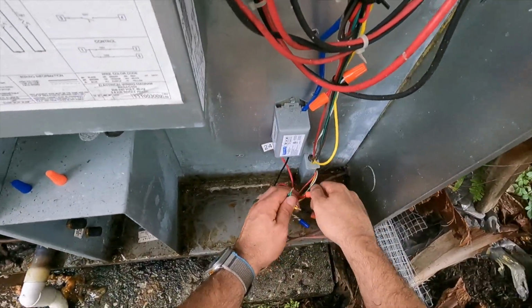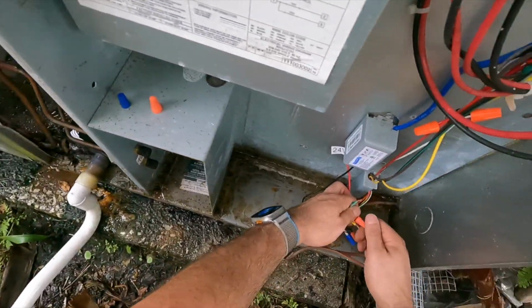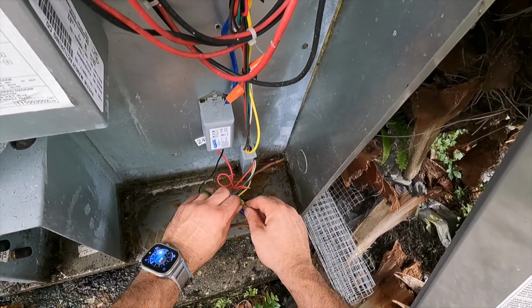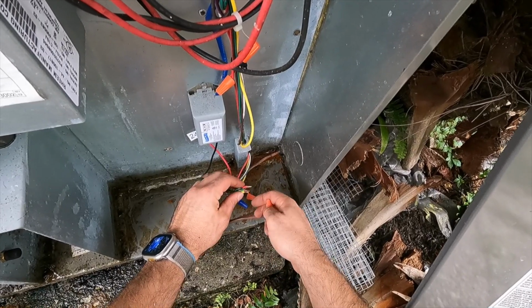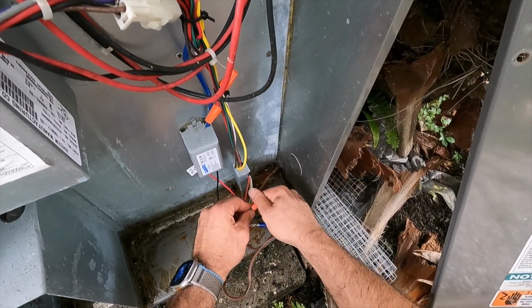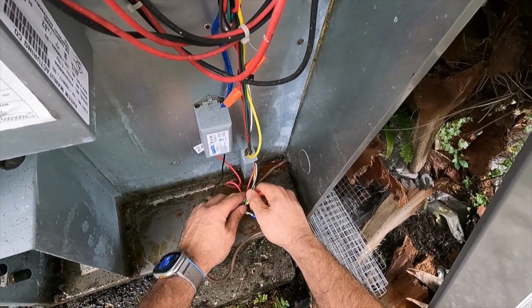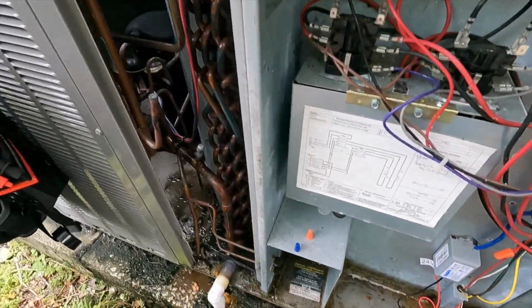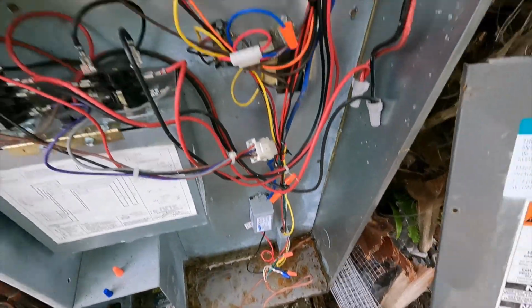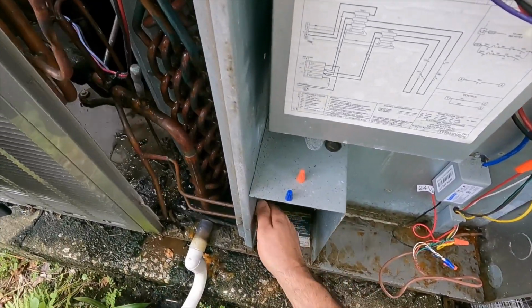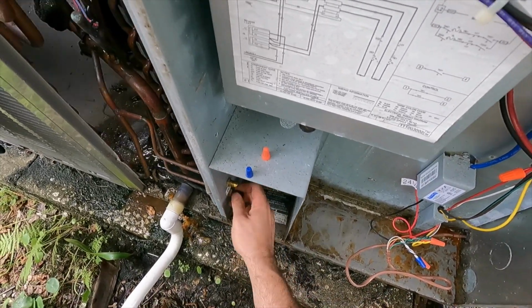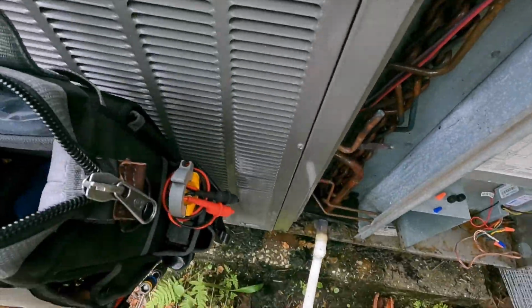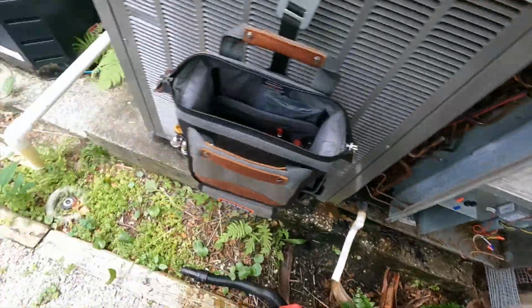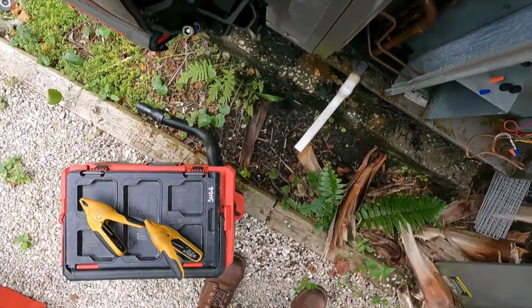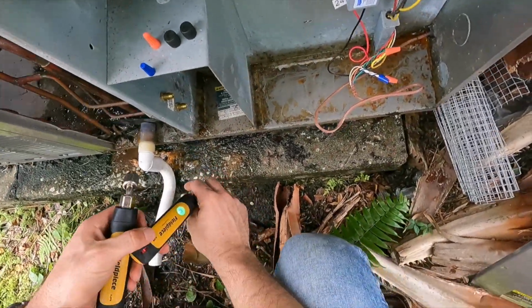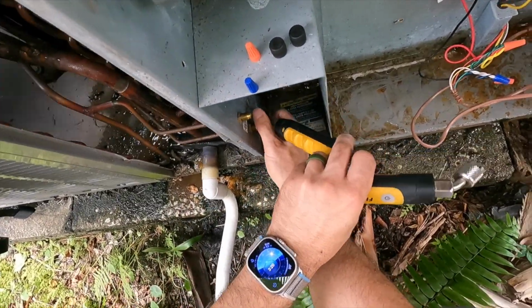I probably need to pull that whole pan. I gotta see if I can do that. Still doesn't look like it's draining right. All right, I gotta do this correctly. There we go. Pretty sure I can pull that whole pan, so we're gonna do that. Let's go ahead and take some measurements first. Sounds like a loose Schrader. Slightly loose Schrader. All right. Meter. Low on the bottom, high on the top, makes sense, right?